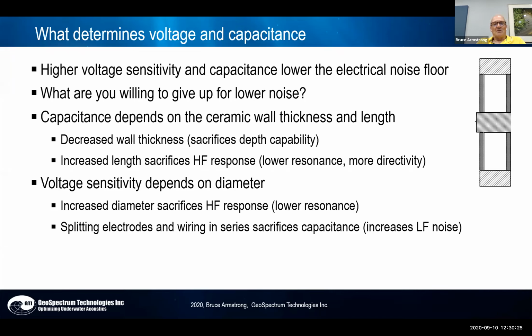The capacitance depends on the ceramic wall thickness and its length. So if I decrease the wall thickness of the ceramic, I get extra capacitance. But what I'm giving up is depth capability. With a thinner wall, I'll crush it at a lesser depth. There's a limit to how thin manufacturers can make ceramics anyway, and most hydrophones are made with a pretty thin ceramic. So making it thinner is not a feasible approach.